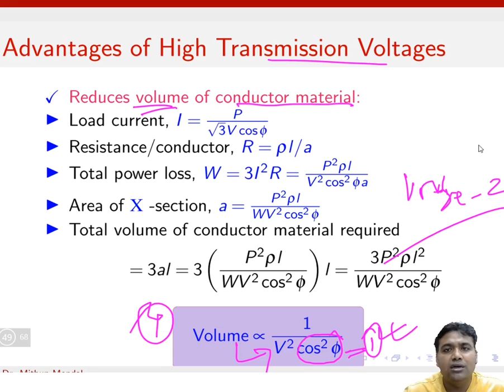If you observe this carefully, the power remains constant in a transmission, the resistivity of the material is constant, and the length of the conductor is constant. So when we talk about the voltage, power factor and the power loss, you will find that the volume of the conductor is inversely proportional to the square of the voltage and the power factor. If you consider the unity power factor condition, the volume is inversely proportional to the square of the voltage. What does it mean? If you increase the voltage two times, the volume of the conductor will be reduced by 4 times. So that is the advantage of high voltage transmission. The first advantage is that it reduces the volume of the conductor material for a high transmission voltage.